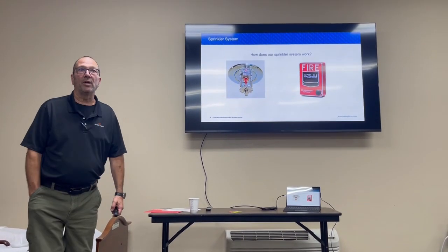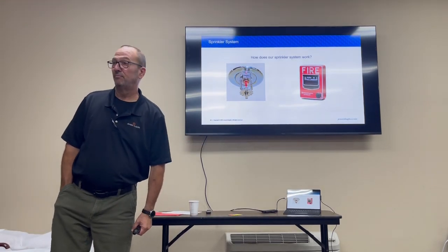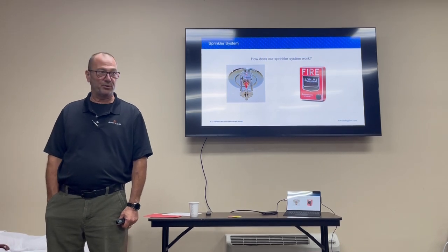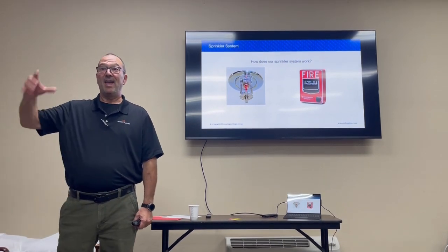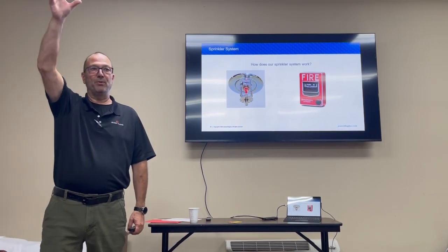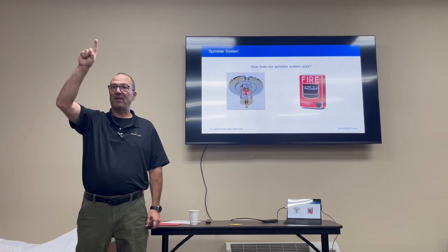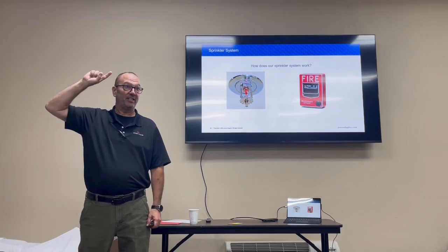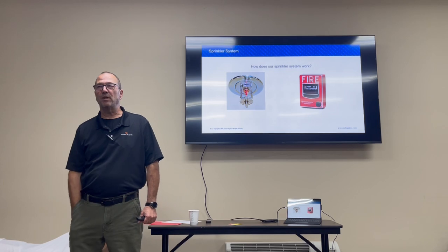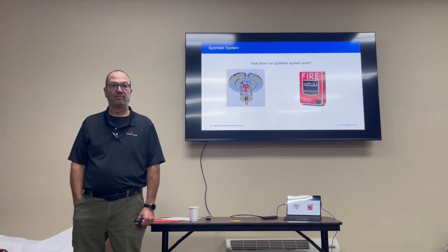So, sprinklers. Your building is 100% sprinkled, right? That's the great news. You want to know what the bad news is? Your building is 100% sprinkled. Here's why. You don't have them in here because this is a business occupancy, but when you get in your building and all those sprinklers are there, each one needs to hit 155 degrees. As it does, it discharges water out in an 8-foot pattern at 20 gallons a minute of the nastiest, stinky, moldy, disgusting water you can imagine coming at you.